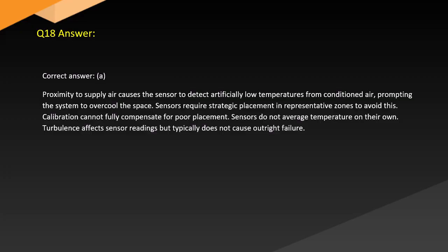Answer. Correct answer. A. Proximity to supply air causes the sensor to detect artificially low temperatures from conditioned air, prompting the system to overcool the space. Sensors require strategic placement in representative zones to avoid this. Calibration cannot fully compensate for poor placement. Sensors do not average temperature on their own. Turbulence affects sensor readings, but typically does not cause outright failure.